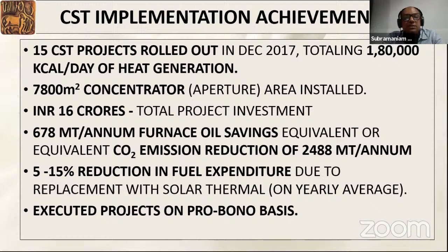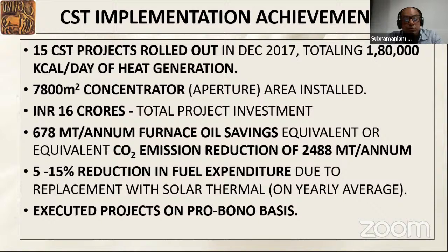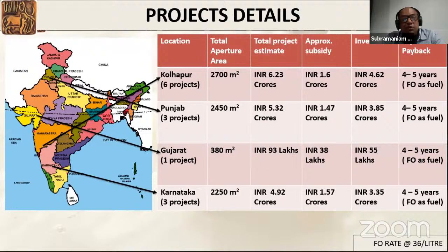In 15 projects completed in 2017, we added around 180,000 kilocalories per day of heat generation, with around 8,000 square meters of concentrated area installed. Total investment was around 16 crores, with equivalent furnace oil savings of 678 metric tons per annum and equivalent CO2 emission reduction of 2,488 metric tons. Installations showed a 5 to 15 percent reduction in fuel expenditure due to solar thermal intervention. NDDB did all 15 projects on a pro bono basis.